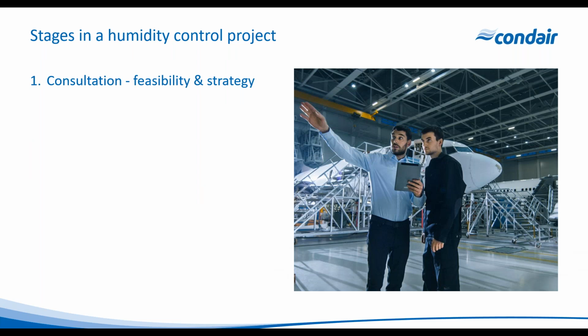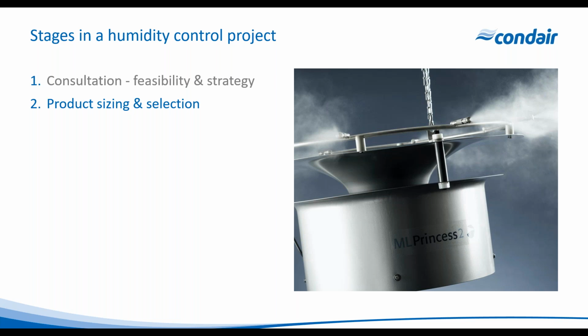So when we look at the stages in a project, firstly, we'll go through the consultation stage, where we'll look at the fabric of the building, the HVAC system, or whether there isn't an HVAC system, the energy sources that are available to you, the quality of the water that's available, and the type of control tolerance that's required in different sections of the application. Once we do that, we'll go through a product sizing and selection process, where we'll be establishing the air change rate or the fresh air rate going into a space, and we'll be looking at the difference in absolute moisture content between winter design and internal set point. So we'll know how much air we're dealing with and how much moisture we're going to have to add to the air. And we'll then look at the other considerations for controllability, for selecting the correct equipment for the application.